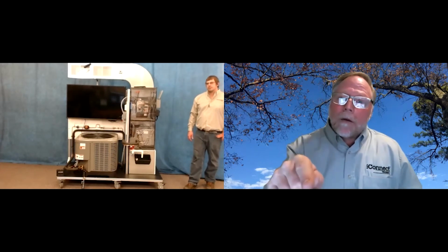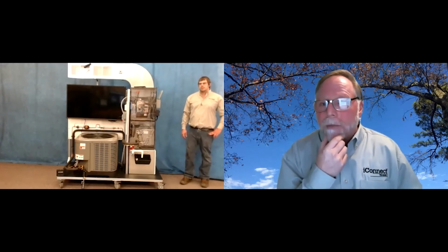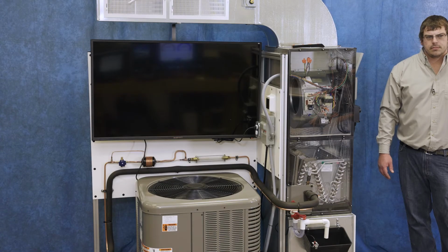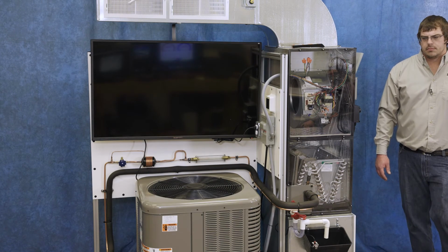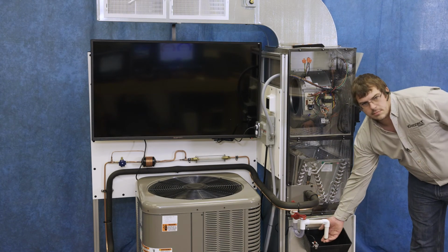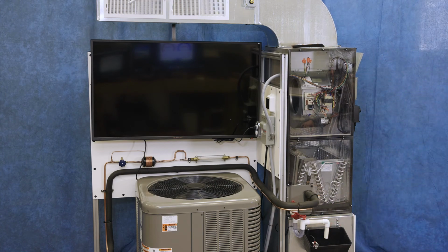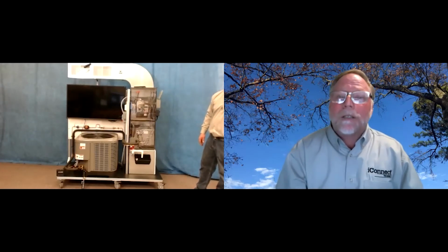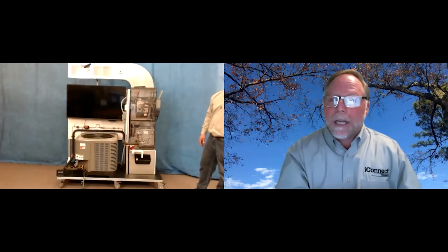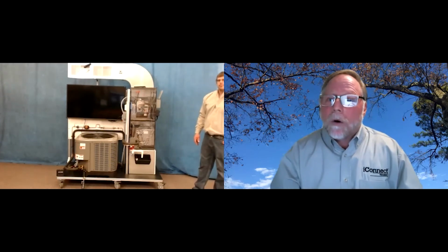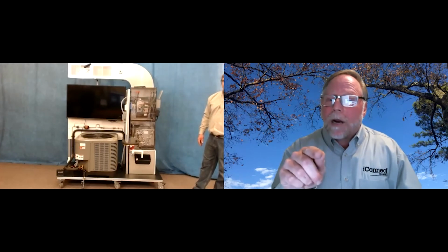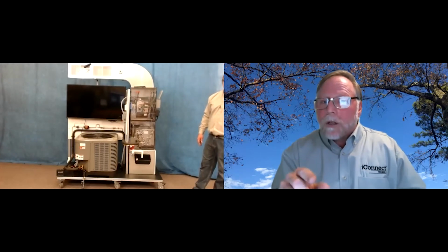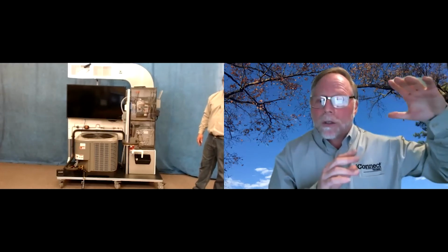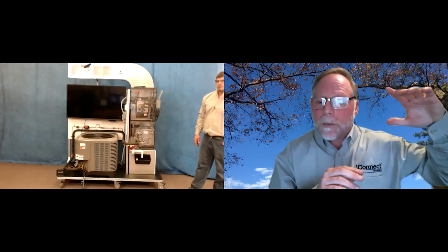Okay, now Nick, as we're looking at it, and we'd be collecting condensation in that drain trap, you could put your hand underneath that drain, and you could actually feel it sucking air. One thing you could do to show the students that is you could take a piece of paper or a tissue, and it would actually draw it up against that trap, and you would show that that trap was actually in a negative pull. So one thing I want to show too, Nick, is that whenever we've got the airflow lowering down, you can also look at the temperature changes across the evaporator from the return to the supply. So we've got those numbers we can show, Nick.